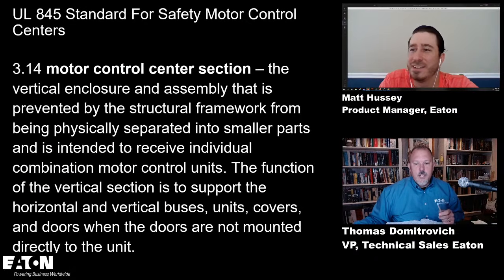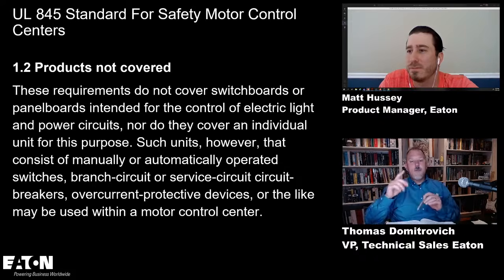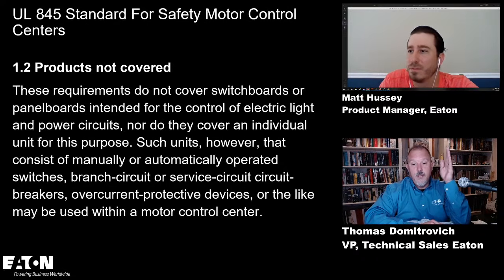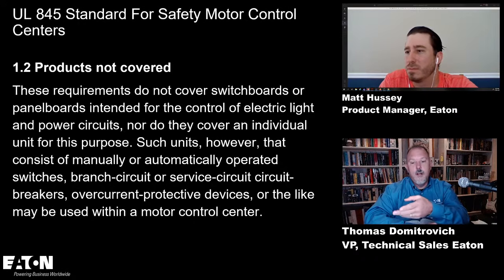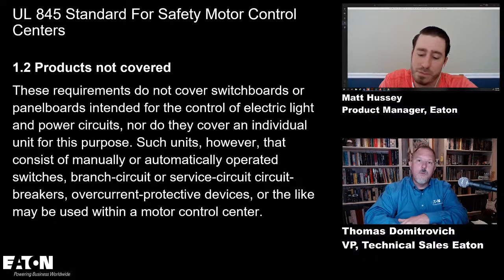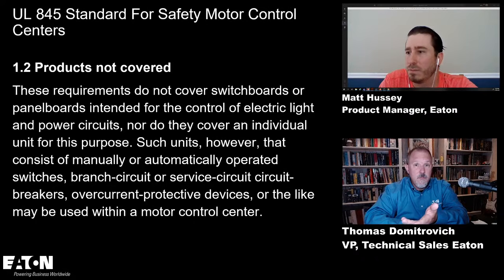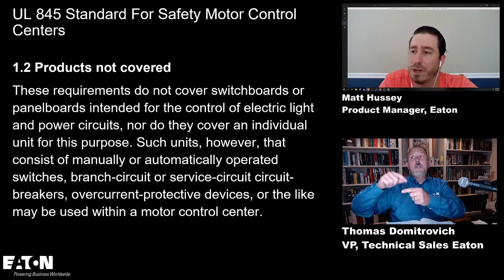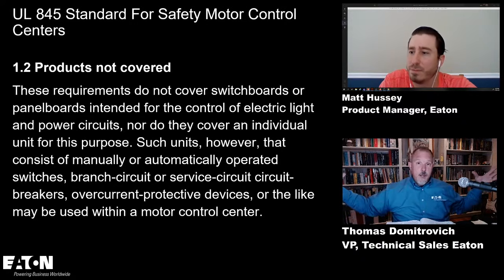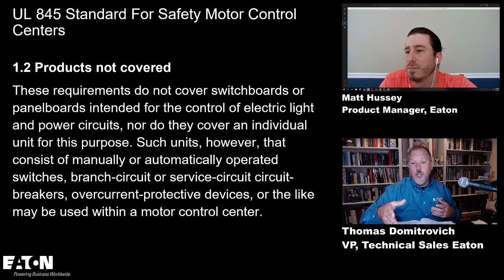All right, so the function of the vertical section is to support the horizontal and vertical buses, units, covers, doors, all that good stuff. Now this one talks about what's not covered in UL 845, which goes to the question: the requirements do not cover switchboards or panel boards intended for control of electric light or power circuits. Because technically, I could put some of these motor control items inside of a switchboard? You could. Yeah, there could be lighting control and other applications for that. But that would be covered by the switchboard standard, not 845. Correct. Just because you're controlling a motor in a large gray box with a bunch of compartments doesn't mean you are a UL 845 type of structure.